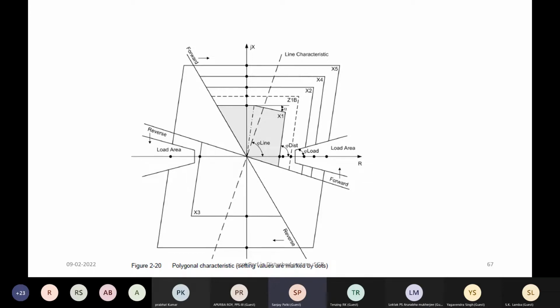So this is the third recommendation. The first recommendation is that all the distance relays at 400 kV lines should preferably be with the polygonal characteristic. Second, the power swing blocking philosophy should be changed. Instead of blocking only zone 2 and zone 3, all three zones should be blocked during power swing, but the tripping with out of step criteria should be implemented. And third, the load encroachment characteristic should be activated so that during dynamic overload condition, tripping due to load encroachment can be prevented.